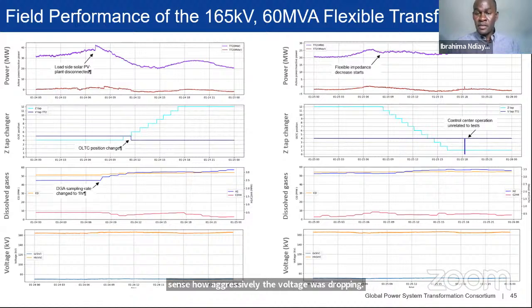And in the other figure on the right side, when we were going in the opposite direction, dropping the impedance tap changer from the highest value to the lowest value, you can see, although the power remained maintained, it suggests more power was coming through the transformer. Again, the natural flow through this transformer is that power will drop around midday and go back to a peak around the 5 p.m. time frame. So that's what we typically call the duck curve.